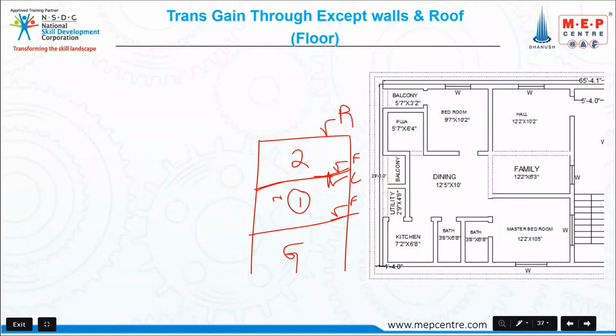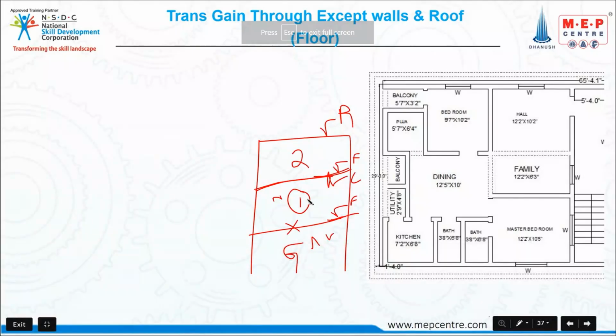Is it clear? Can you please repeat, sir? Suppose this is ceiling now. I am doing calculations for the first floor. Okay, this is floor for me. Ground floor is AC, socho. Should I need to consider the floor in the calculations? Ground floor AC. No, this is not taken. Now I am calculating for the first floor. Now ceiling came. Second floor is non-AC. We have to consider ceiling. So if second floor is AC, then ceiling also will become 0.